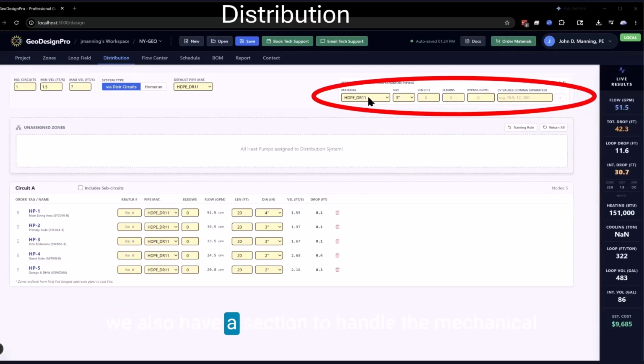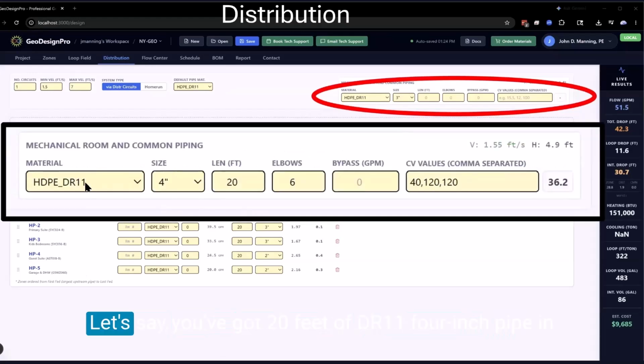We also have a section to handle the mechanical room. And I'll blow that up so it's easier to see. Let's say you've got 20 feet of DR11 4-inch pipe in the mechanical room connecting everything together. You may have 6 elbows. We built in a bypass function so that some guys like to have a continuous side stream filter coming off the discharge of the pump going back into the return. If you want to incorporate that in your design, you put a flow rate here that corresponds to that filter. It goes into the total flow that the pump has to produce, but doesn't change the pressure drop of the system. You can incorporate CVs of the various hardware.